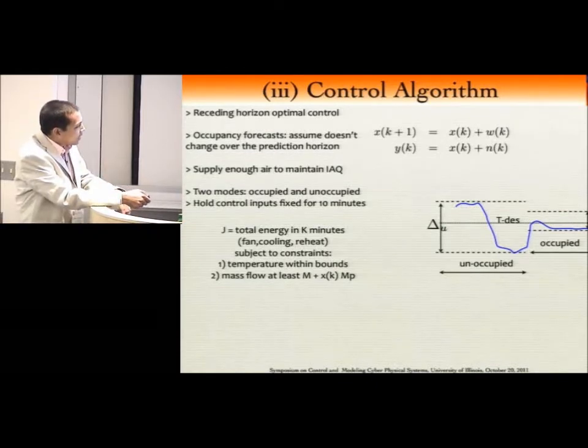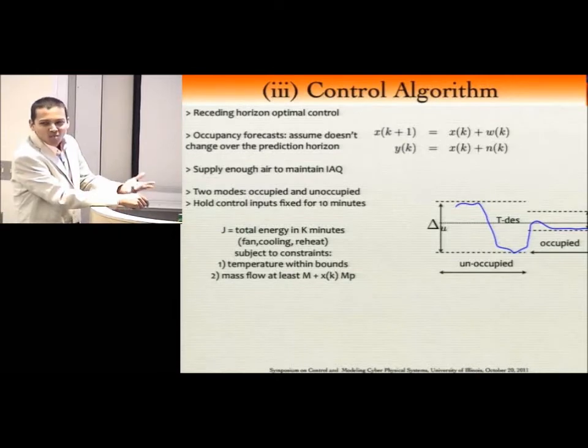And the fact that this blue curve, which is the zone temperature, goes to the lower level of the allowable limit is not an accident, although this was drawn by hand. If the AHU supplies air at 55 degrees, and you ask it to optimize energy consumption subject to this constraint, guess where it's going to go? It's going to go to the lower limit, right?